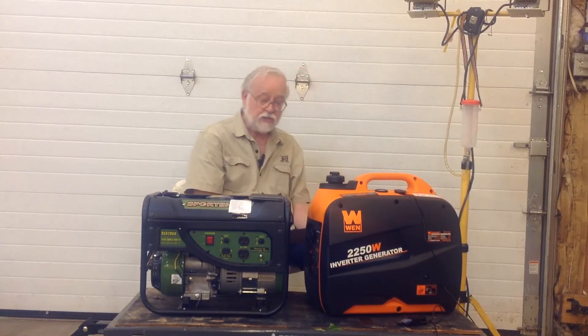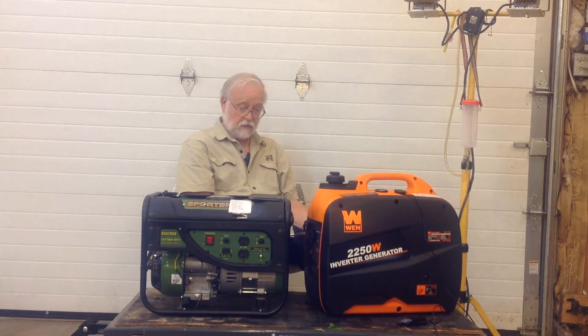Watching a fuel test is about as interesting as watching paint dry, so I'm going to show you several clips made during the testing process, starting with the WEN generator first. You will see the generator loaded to about 464 watts, and in the second clip loaded to about 905 watts. Please note the stable operation of the power monitor on the load bank and the smooth waveform as seen on the oscilloscope.